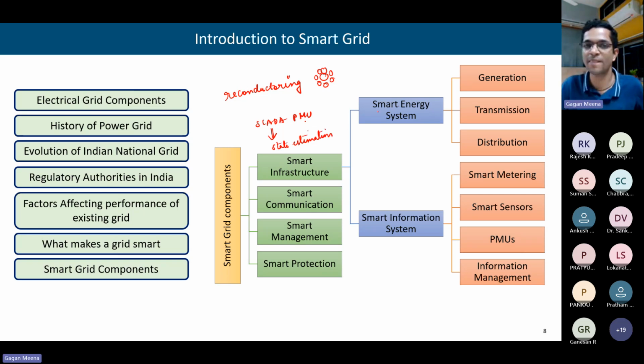And if we replace SCADA by PMU, let's say in 8,000 buses, 500 buses have PMU and the rest 7,500 buses have SCADA, the rate at which these two systems provide data is very different. Second, the data we get from SCADA is not time stamped. We don't know which particular sample corresponds to which time instant. So how do we compare the two data if we don't know? We can only compare when the two values belong to a particular time instant. But if they belong to different time instants, then that is of no use for us.